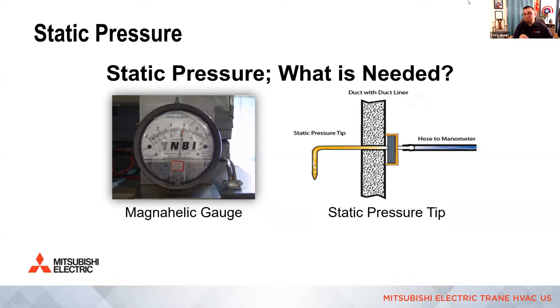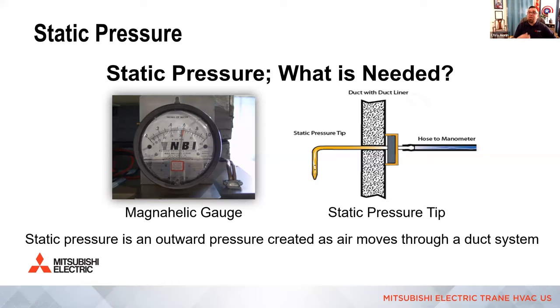And then of course, a static pressure probe, not a pitot tube. A pitot tube will measure total pressure. Static pressure tips, when you point them into the airstream, will measure the pressure on the duct system only, okay? So it excludes velocity pressure. You'll notice the tip is blanked off here and there's just holes on the side. If I turn that pressure probe the wrong way, it would measure velocity, not pressure, right? So it's really important you're using it correctly and you measure in the right spot. This can give you a great indication as to what the volume of air is on the old system or what the static pressure is on the old system before you make a replacement or an adjustment, all right?